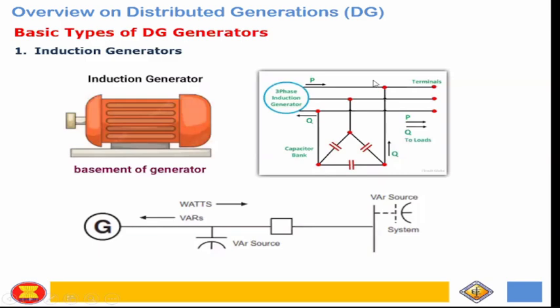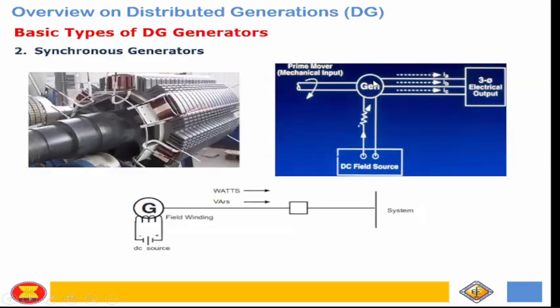Okay? So while the synchronous generator has a field winding to provide the source of machine excitation, siya yung magpo-produce ng kVAR, while it distributes real power, and it can support kVAR as well, the reactive power. Then this system requires synchronizing equipment. May synchronizing system to monitor the voltage, if they are in phase, the voltage, the frequency, and then the angle deviation. Yun yung before synchronizing to the grid.